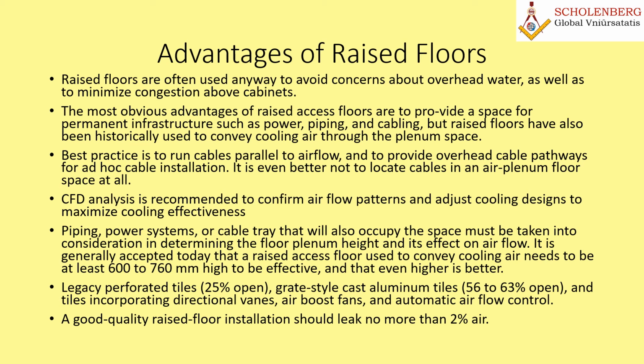That's the beauty. Based on that, we can keep the perforated tile locations near to each machine. So where a particular machine is generating high heat, we can keep two or more tiles based on the equipment manufacturer specification or the air requirement of that particular machine. So based on that, we can fairly distribute the locations and perforated tile types near to each machine.